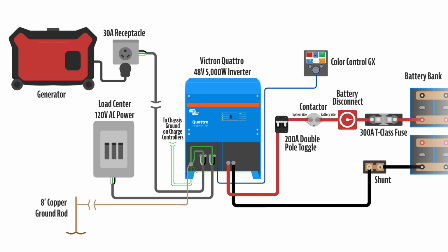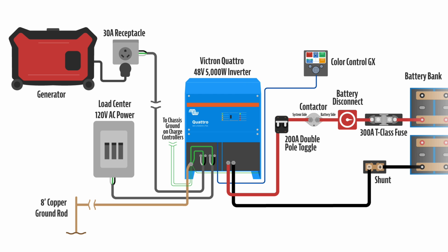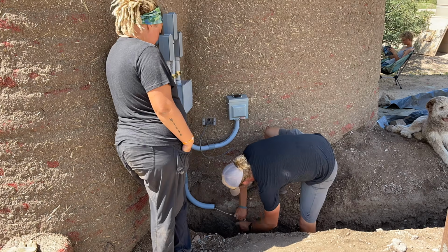The Quattro requires all grounding cables to be connected together. Not only does the AC out need its ground connected to the ground post and the AC in, but also grounding chassis from your solar charge controllers and from the inverter itself, which is kind of weird. That all connects to a single post, which then runs a bare 6-gauge copper wire out to another 8-foot ground rod on the outside of the building.